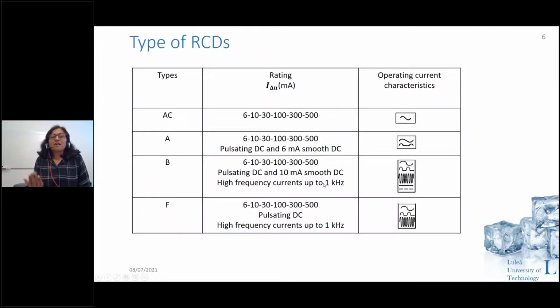So there are different types of waveform distortion. There are different types of RCDs also, and the oldest one is the type AC RCD, which is meant just for pure AC. It just detects pure AC current in the leakage current and trips based on that. It has several ratings: 6, 10 milliampere, 30 milliampere, 100 milliampere, 300, and 500 milliampere. Out of which, up to 30 milliampere the RCDs are used for human protection, and above 30 milliampere the RCDs are used for fire hazard protection.